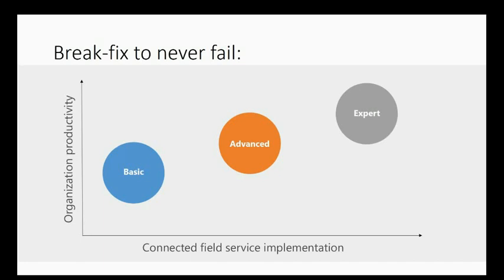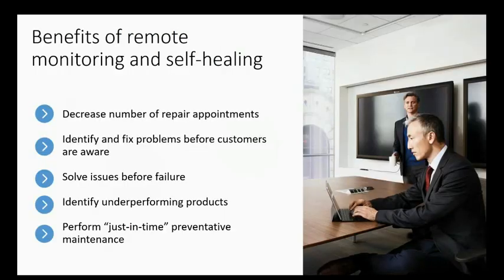So to recap on monitoring and self-healing, the real benefits are, first, decreasing the number of repair appointments. If you need maintenance on a piece of equipment every 10,000 hours, and you actually show up when you're at 10,000 hours versus when you think it is, you reduce the number of appointments. You can identify and fix problems very often before the customer is even aware.